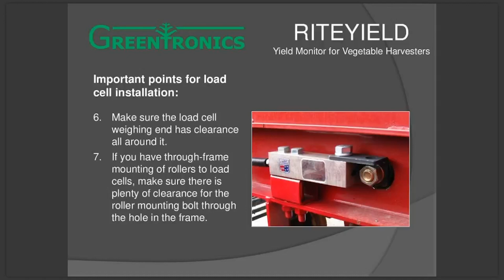As I said before, my personal preference is that the load cells should be mounted on the outside of the conveyor frame. That way they're a little bit less likely to get gummed up with dirt. It's also easier to run the cable in a safe place. There's an arrow on the weighing end of the load cell, and it should be pointing down. And it is, don't joke, it goes wrong sometimes, and you get negative numbers. So it's easy to check, though.